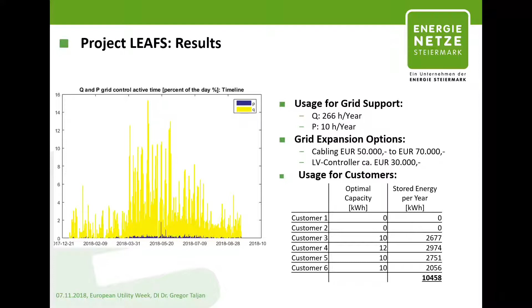Grid expansion options - we calculated that as well. Cabling would cost us, in this concrete case, roughly between 50 and 70,000 euros. We could also install a low voltage grid controller for 30,000 euros, and these costs are the limit of how much we as DSO are prepared to co-finance the storage system, with the rest coming from consumers. We have 6 consumers with 10 PV installations connected, and they store roughly about 10,500 kilowatt hours annually into the storage.